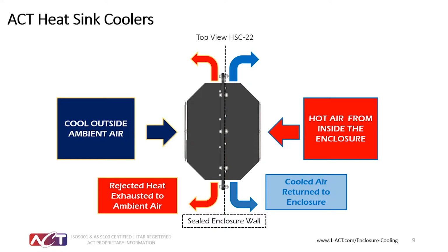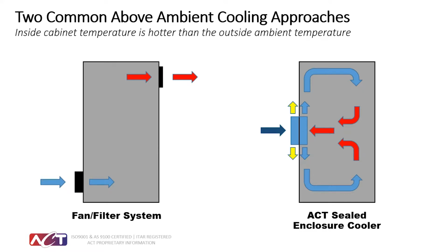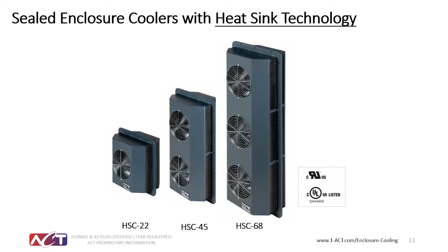Integrated inner and outer cabinet circulating fans blow over the surface of the fins, enhancing the heat transfer. In contrast, fan filter systems cool the cabinet by drawing in potentially contaminated external air and circulating it throughout the inside of the enclosure. ACT's HSC series of enclosure coolers are based on a patent-pending design that utilizes an air impingement technology that is thermally efficient and enhanced by thermal bonded finned heat sink components. As a result, the ACT HSC series offers some of the best performance-cost ratios among all sealed enclosure cooling technologies.